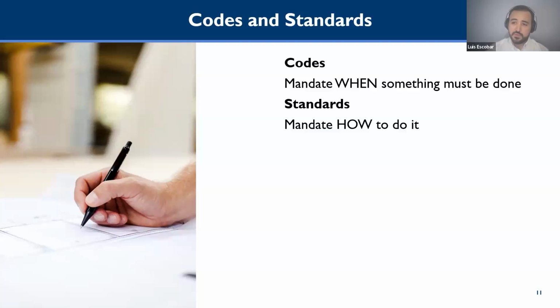Codes and standards. What's the main difference? Two words: when and how. Codes mandate when something must be done. And we're going to focus on this one, standards, as NFPA 13 is a standard for the sprinkler installation. NFPA 13 mandates how to do it: how to install the fire sprinklers, how to install the piping, if we need to slope it, if we need a certain type of pipe for each application, or if it has to be underground, or it has to be exposed to the exterior, all that. So we're going to be digging more into this.